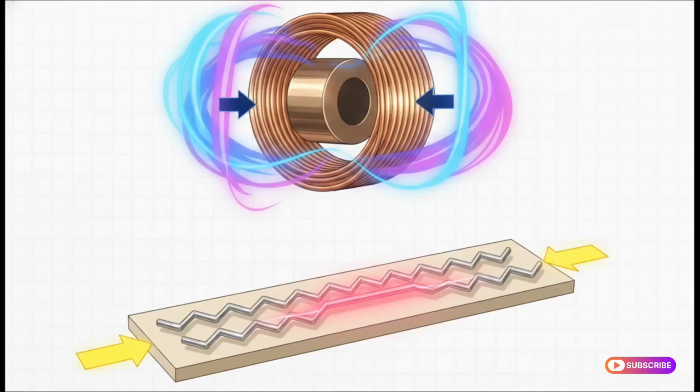First up, you need to know about the inductance coil method of an indicating element. This involves shifting an iron armature inside a transformer coil. As the pressure moves the armature, it changes the magnetic field, the inductance, which directly alters the electrical voltage output. Alternatively, we have the resistance rod indicating element, often using what's called a strain gauge. Here, microscopic wire elements are literally stretched or compressed by the physical force. As the wire stretches, it gets thinner and its electrical resistance naturally increases. In both cases, we are magically turning microscopic physical changes into highly accurate, easily transmitted electrical signals.